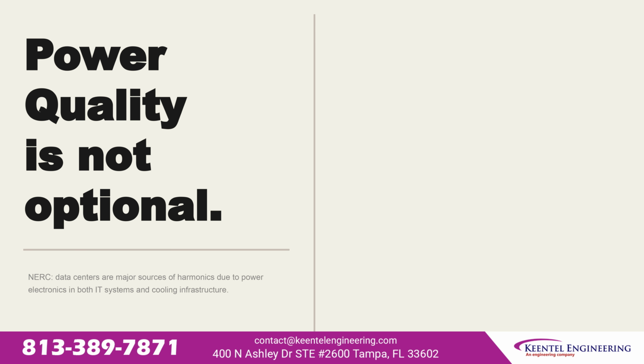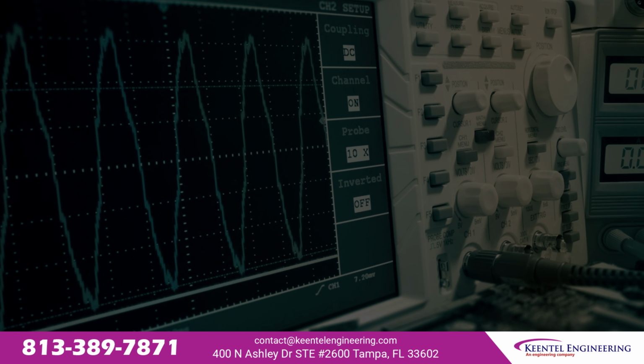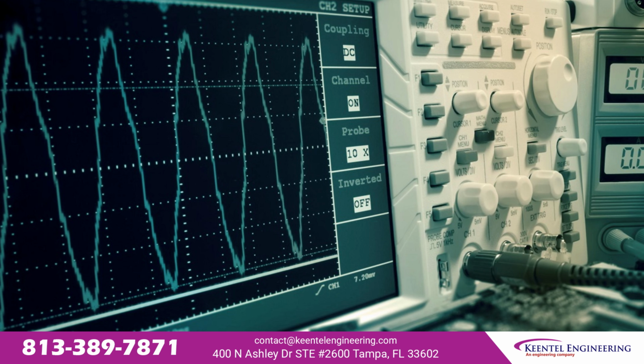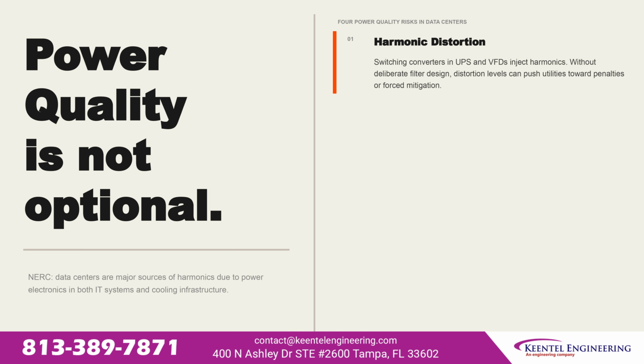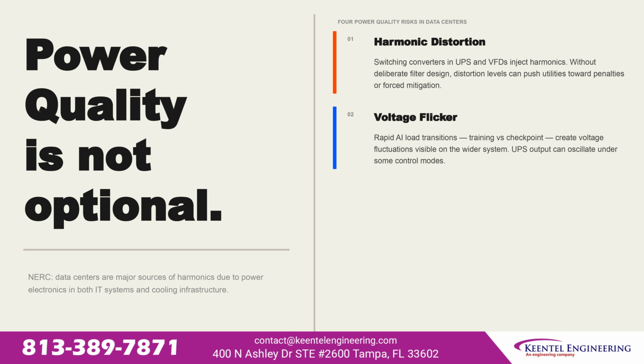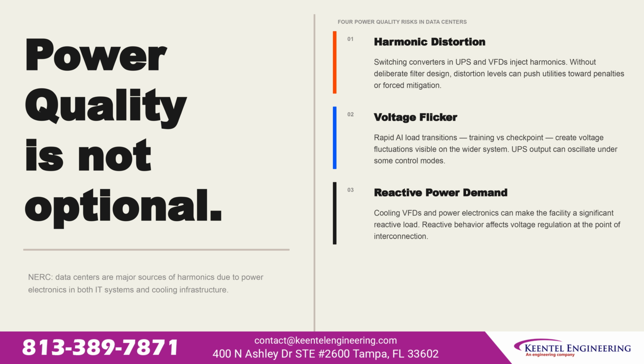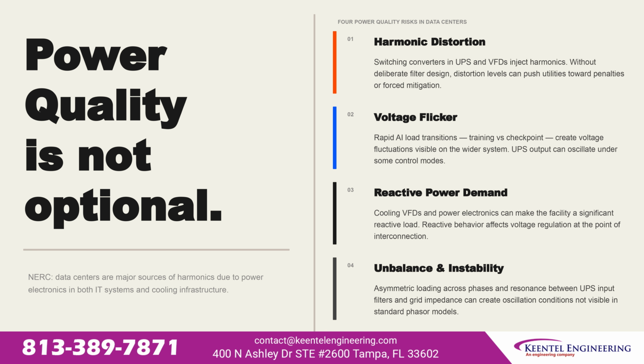NERC is direct. Data centers are major sources of harmonics due to power electronics in both IT systems and cooling infrastructure. 4 risks. 1. Harmonic distortion. Switching converters in UPS and VFDs inject harmonics. Without deliberate filter design, distortion levels push utilities toward penalties or forced mitigation. 2. Voltage flicker. Rapid AI load transitions create voltage fluctuations visible on the wider system. UPS output can oscillate under some control modes. 3. Reactive power demand. Cooling VFDs and power electronics make the facility a significant reactive load, affecting voltage regulation at the point of interconnection. 4. Unbalance and instability. Asymmetric loading and resonance between UPS input filters and grid impedance create oscillation conditions that standard phasor models don't see.